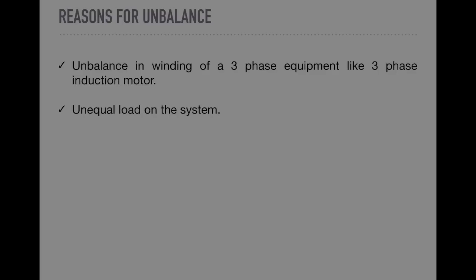Such kind of unbalance causes heating of three phase machines. Further, this will decrease their overall life. This imbalance will also increase the I2R losses. Also, unbalanced system may cause tripping of variable frequency drives used for induction motor.